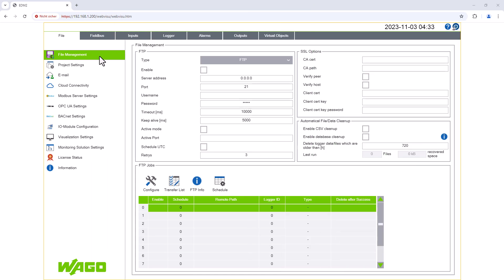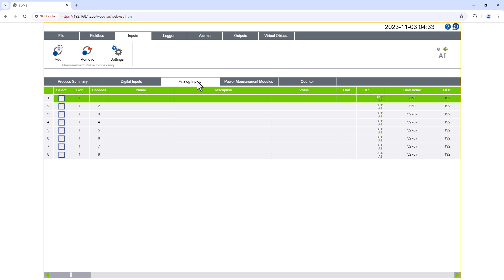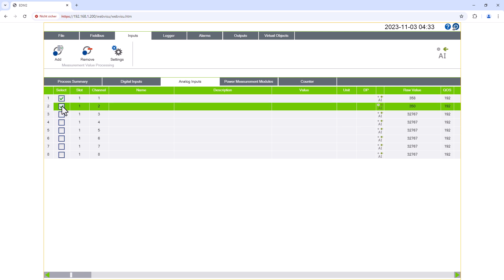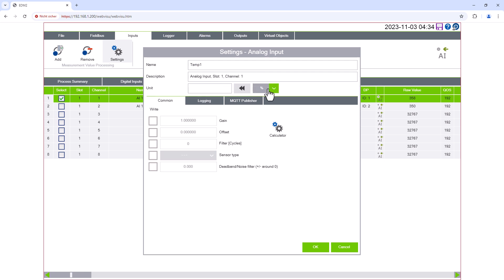In EDM, we first need to create the two measurements as analog inputs. To do this, go to the Analog Inputs menu in the Inputs menu. The eight inputs of the input terminal are displayed and we can add the required channels to our EDM project by clicking on the Add button. We use the Settings button to assign a name, set the unit and find all the other settings necessary for temperature sensors.